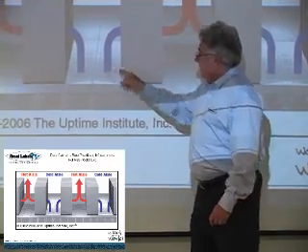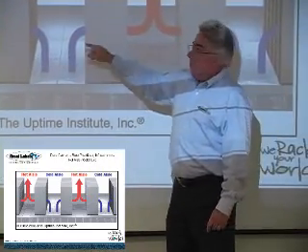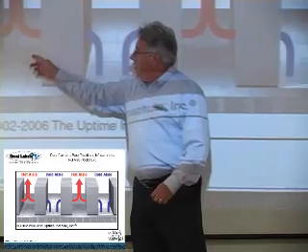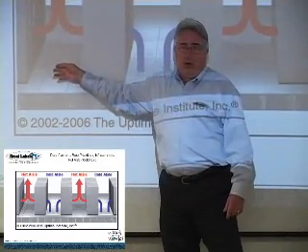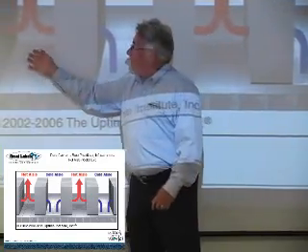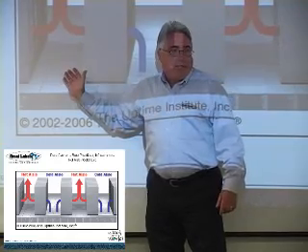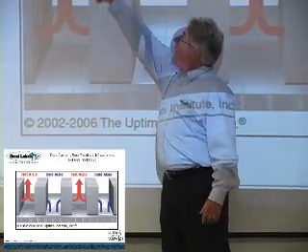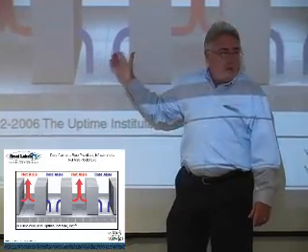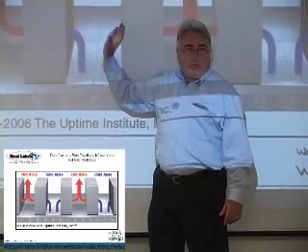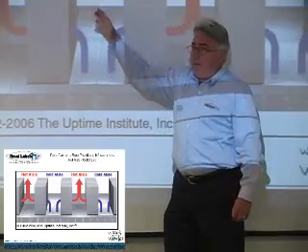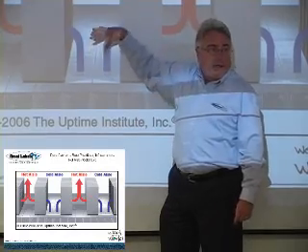But if you look at this, you'll notice that there's really only vents in the cold aisle. Okay? Oftentimes you can think of your own places. Hopefully no one raises their hand, but you don't have vents or perf floor tiles in your hot aisle. What we found there is once you start putting vents in your hot aisle, now you're shoving the hot air up, and it can now be recirculated into here. If you keep just perf tiles in the cold aisle, you're creating positive pressure here. You will get no circulation over, or very little. So make sure that your perf tiles are only in the cold aisle.